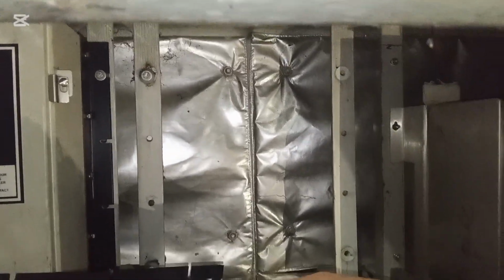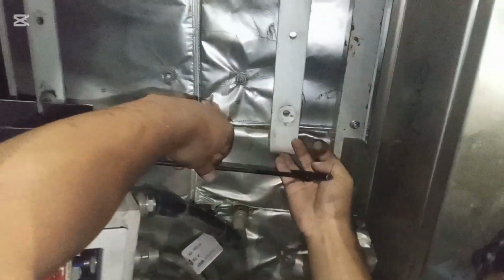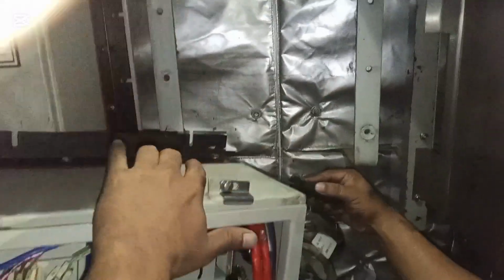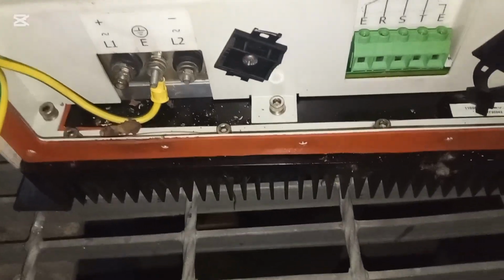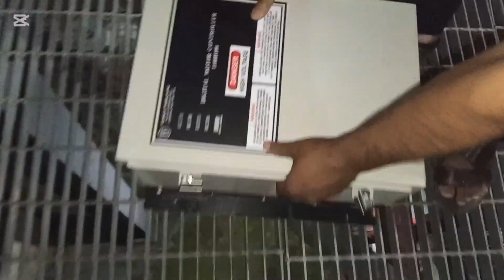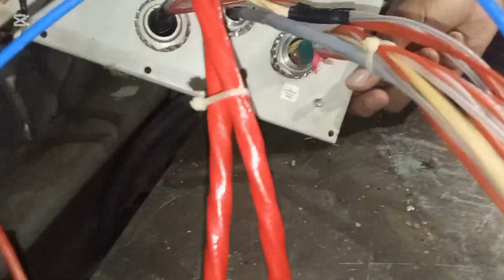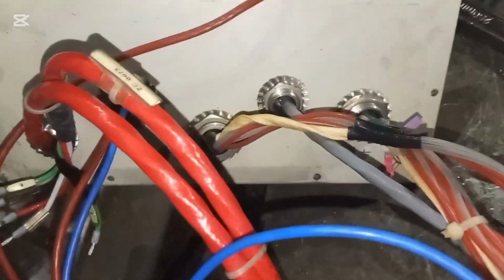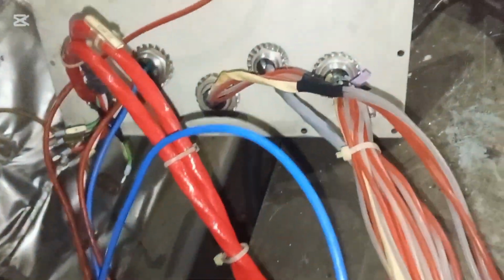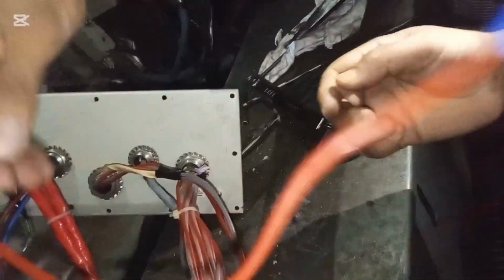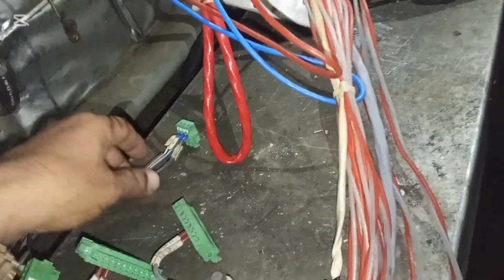To dismantle the bottom cover with the cable connector took some time, and the screws were too tightly fastened, and then we opened the screws from the controller base. This is the new controller unit. At the time of dismantling the cable, there were 6 single cables, and we marked the cables considering their color and tag number so that the connection would be properly right. And then we dismantled the bottom cover with all the cable connectors.